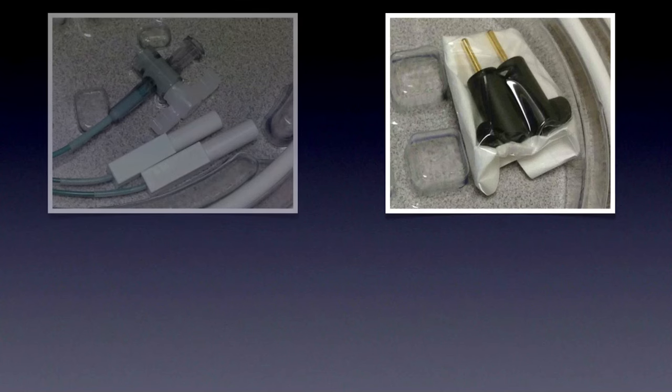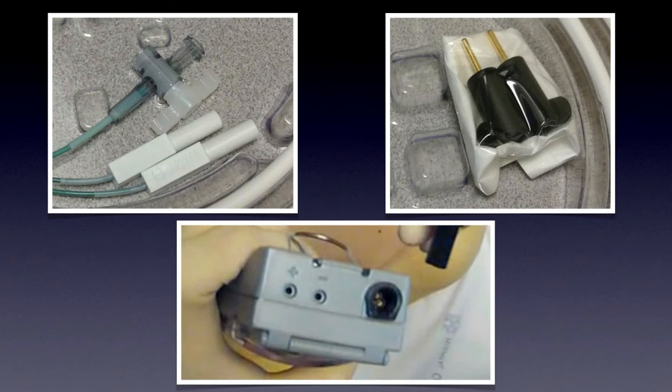The pin connectors can be attached to the electrode leads of your pacing catheter. One use is to attach an alligator clamp or EKG lead so you can sense waveforms and determine catheter position — right atrial, right ventricular, pulmonary artery, or IVC. They can also plug directly into the positive and negative ports on the generator, but those pin connectors slide in and out very easily, and disconnection is dangerous when you're trying to stabilize a rhythm.